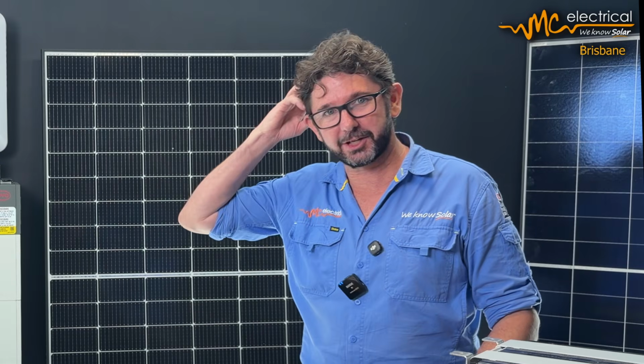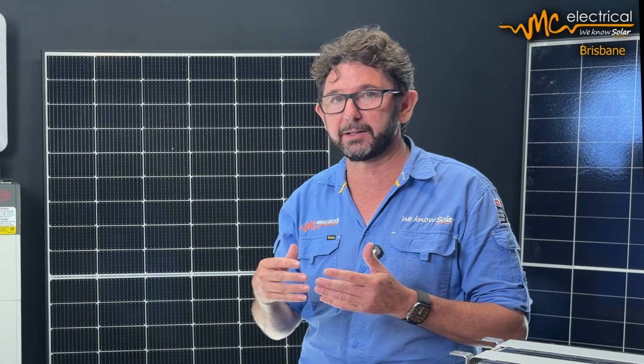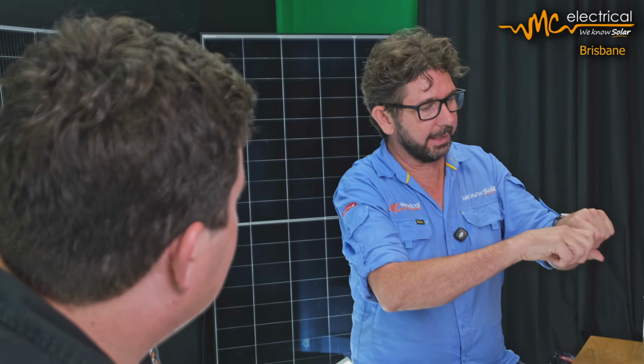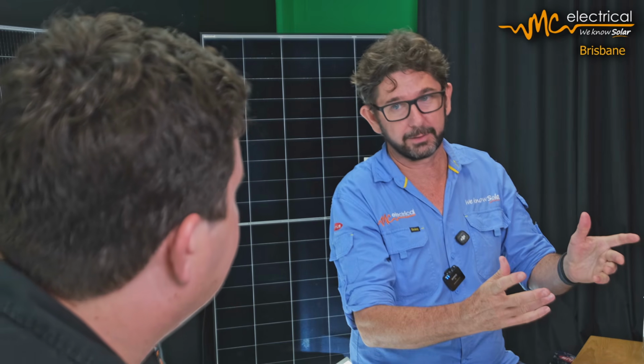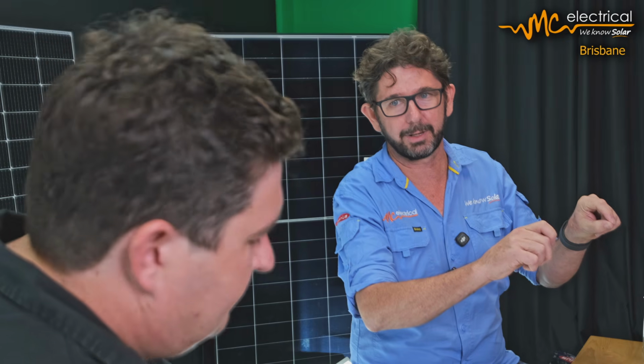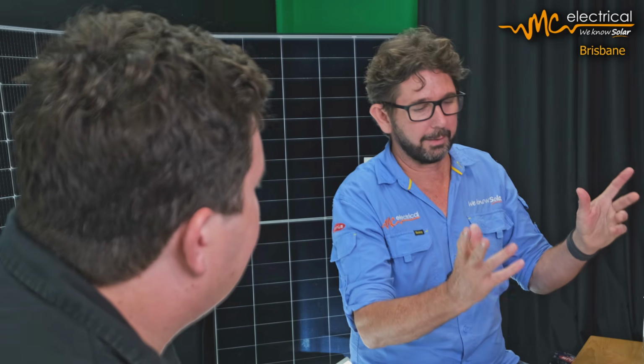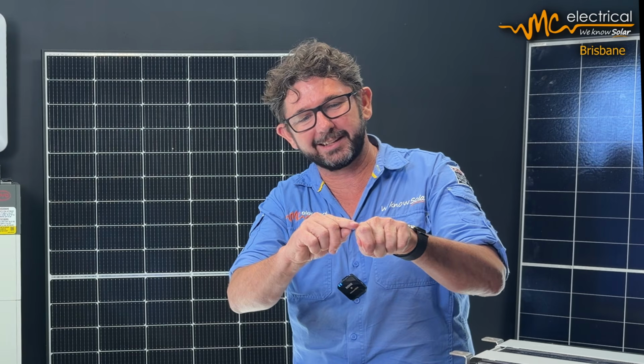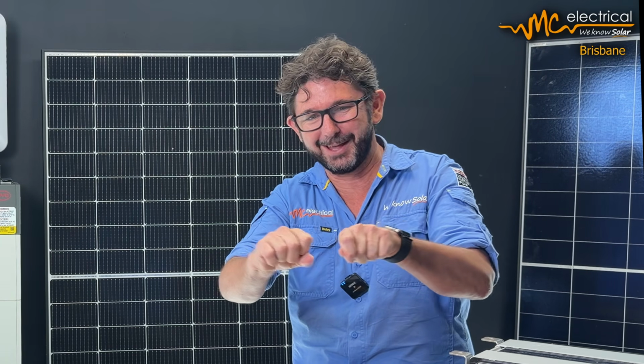When we're doing these shading tests, we're changing out arrays all the time, switching this array over to that one. So I told Tack, my apprentice who helps with a lot of testing, to run down and undo that MC4 plug and change it over to the other array. He went down to unplug it - I've done this a thousand times, and technically you shouldn't undo a plug under load, gotta give the apprentice a break, but I do it all the time, you can get away with it, it's completely fine. But he undid it and saw this massive banana arc as he undid it. I don't know why, but it blew up the inverter.